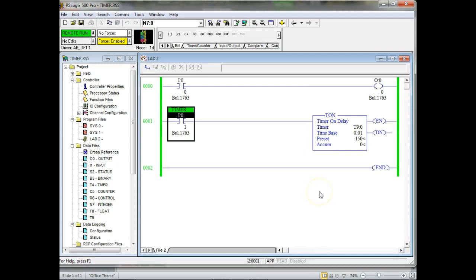So are we okay? So we're not using something, but as soon as we energize the switch, it shows us the flow, right? So this is a very, very good troubleshooting aid. And then when we energize the timer, it should do what? You know. And then, so we're using the enable and the reset is the same thing. So this guy right here automatically resets the accumulator to what? When you disable the timer. Disable it. Are we okay? You're saying when you flip it back off, it resets automatically. Yeah, so if you loaded it with a number, you'd have to reload it.